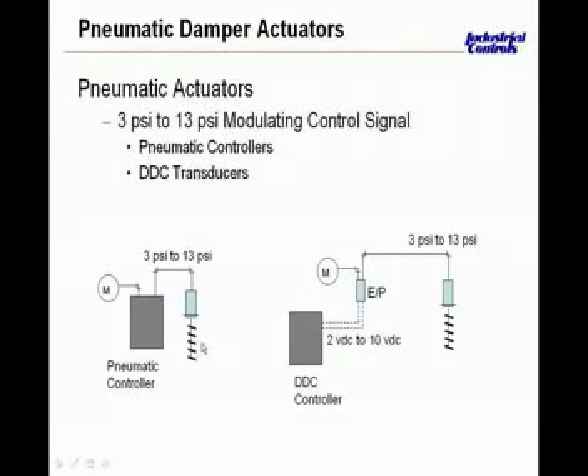So now if we take the same controller as far as the air pressure goes, we now have main air coming into an EP, which is actually an electric to pneumatic transducer, that's going to convert the signal coming from main air coming through here and change this line going to 3 to 13 pounds. And it does so by changing, instead of having an air pressure coming in here, we are now showing a DDC or direct digital controller that's going to change the signal from 2 volts DC, modulating it all the way up to 10 volts DC, which would then be changing the air pressure going in here.